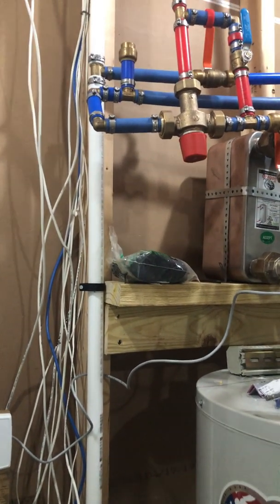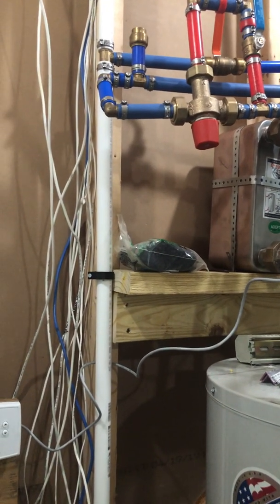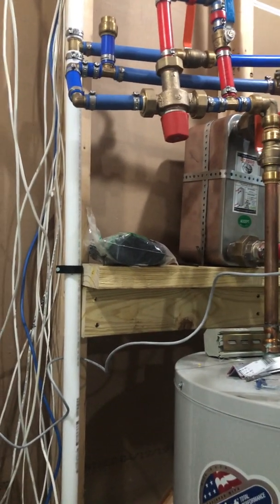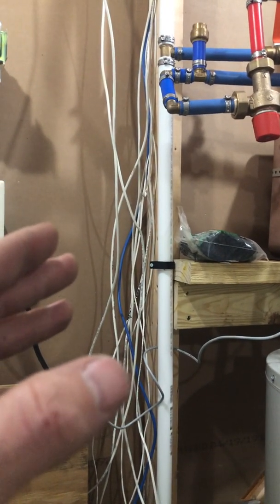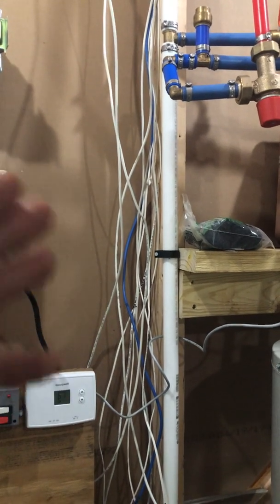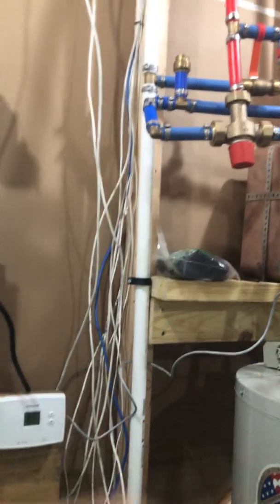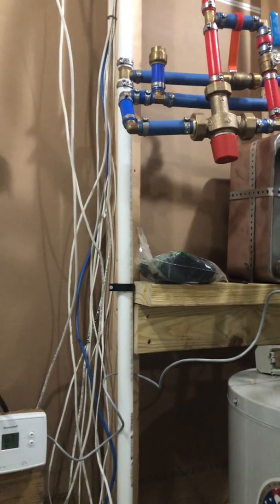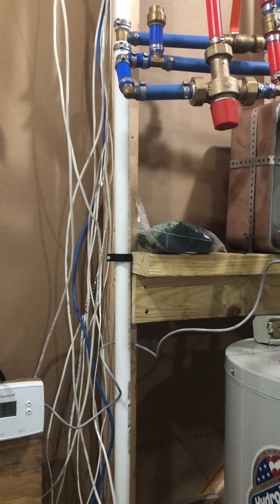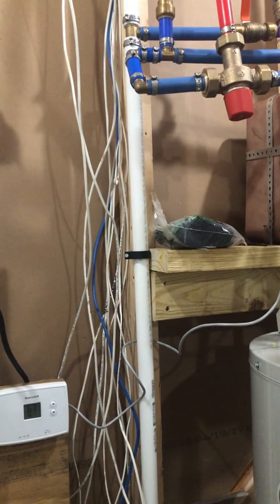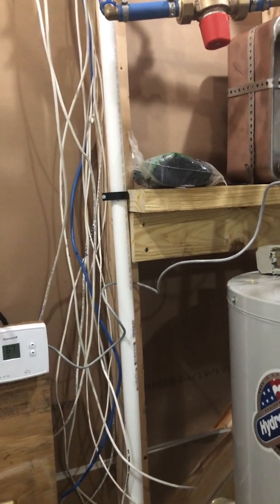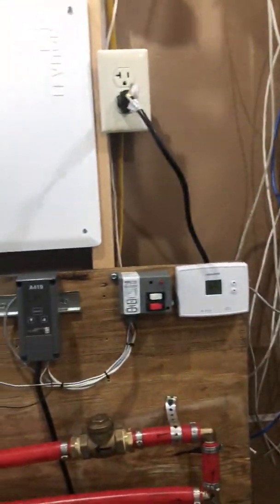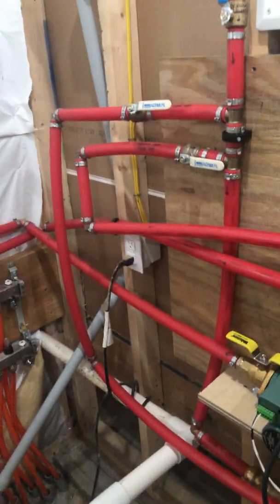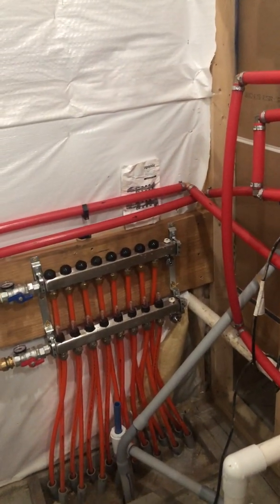I didn't have to carry a hose out there. I can just add in. And the reason that works and you don't contaminate your potable water is that the pressure on the boiler is only, even with the pumps running, a couple pounds of pressure, maybe up to 10. And the pressure on the water coming in from the street is higher than that. So when you open that valve, it's going to push water into the boiler system, and then you close that off and it's no problem. So anyway, that is my system, and I'll show you another video when I get that fire rolling.